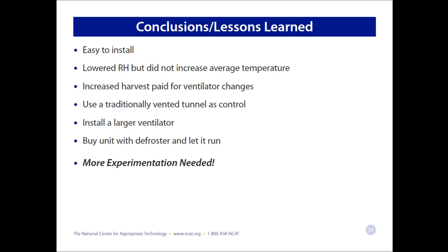I would also install a larger ventilation system. I would move up to that 200 CFM unit for the tunnel's size that we were dealing with in this experiment, the 20 by 96. I would go up to a 200 CFM unit and see if that made a larger difference, see if we could get down to that 85% humidity or lower.